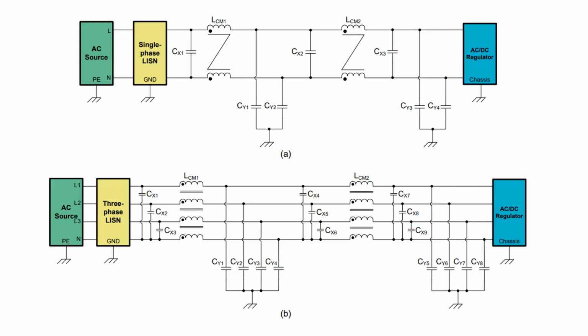Complying with EMC regulations intended to limit the levels of conducted emissions requires the insertion of a low-pass EMI filter between a switching regulator and a mains input source. This setup illustrates typical filter arrangements for single-phase, 3-wire, and 3-phase, 4-wire systems in kilowatt scale, grid-connected applications. L, N, and PE refer to live, neutral, and protective earth terminals. Multi-stage filters, as shown, actually provide high roll-off and are common in high-power AC line applications, where common mode noise is often more challenging to mitigate than differential mode noise.